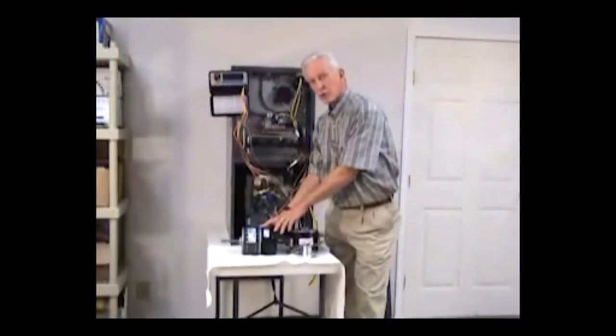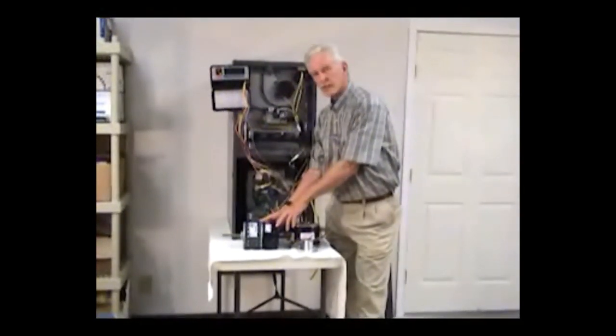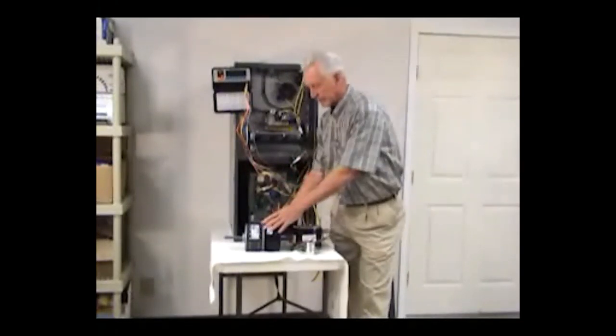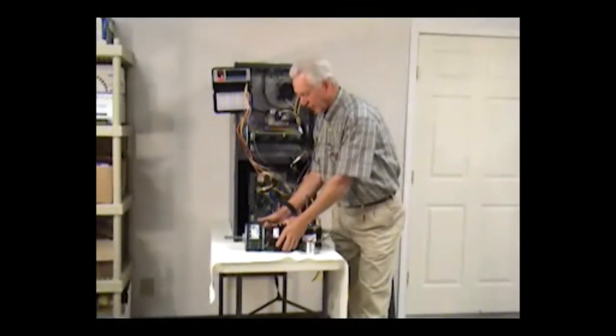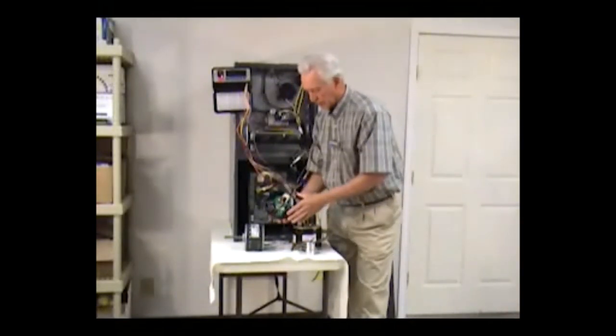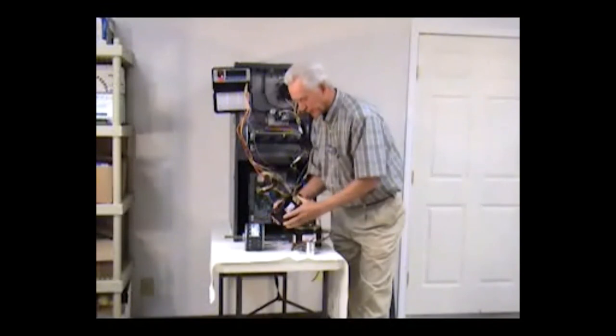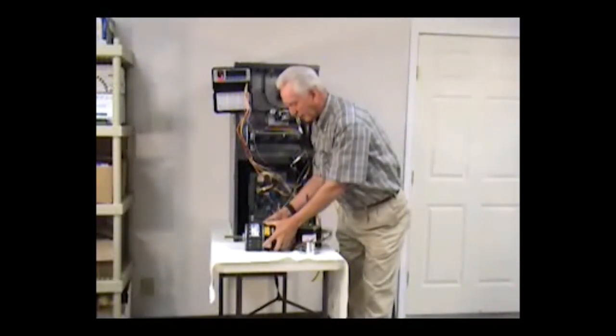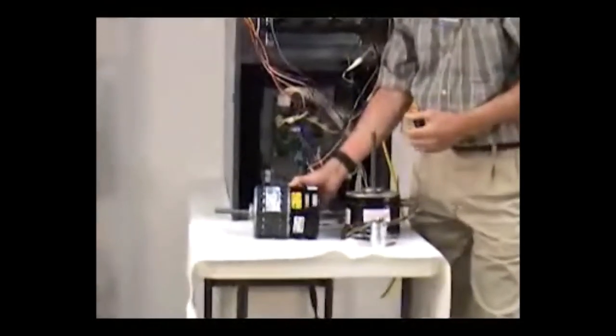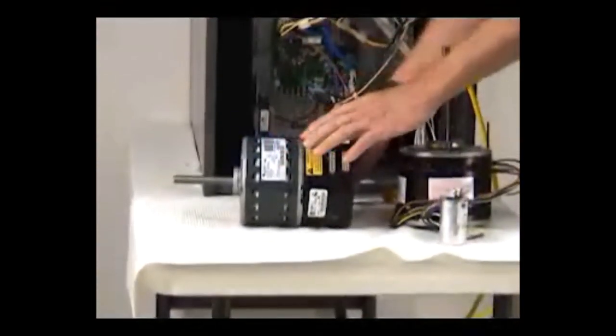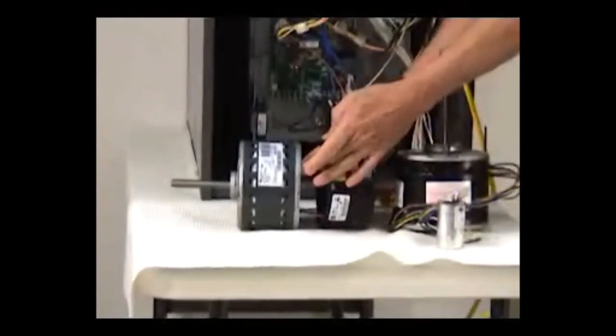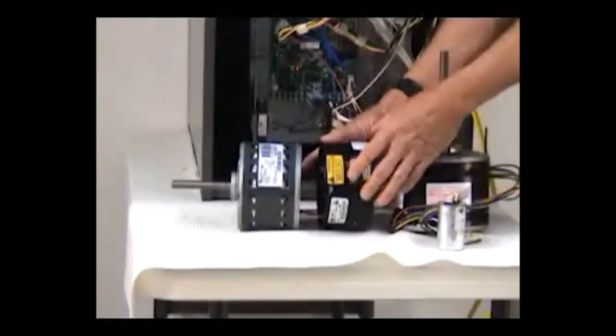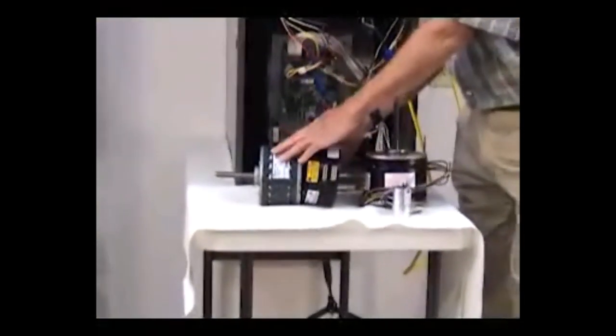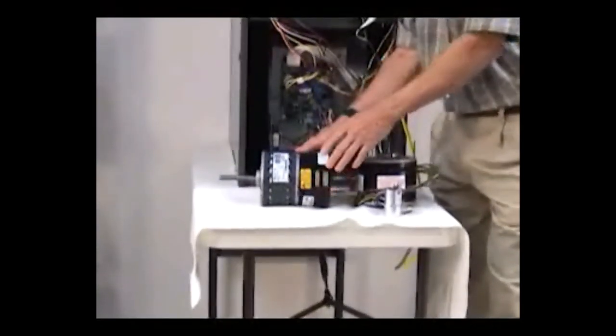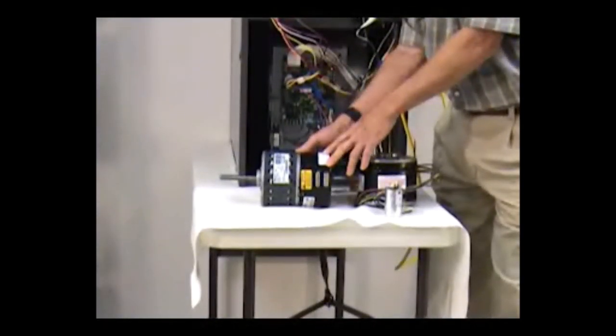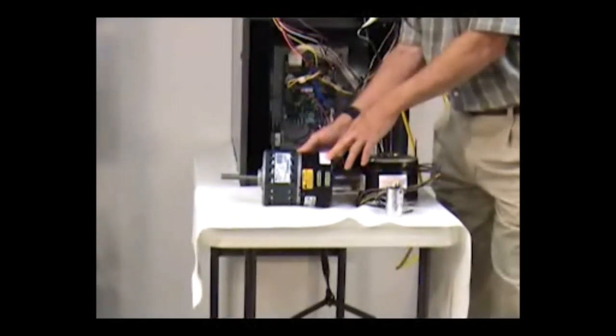Then they came out with the 2.3, which is probably the one that is the most predominant now, and is this particular model that we are looking at right here, where this is plugged in to your module here. The three-phase section of the motor is plugged into the module and then attached to the back of the motor itself. You can take older motors and upgrade those older motors with the silver back that is attached to it, or module, and you can upgrade those, still keeping the same motor, the older motor, with the newer 2.3 module attached to the back of that motor. So there are upgrades to those motors currently as we speak.